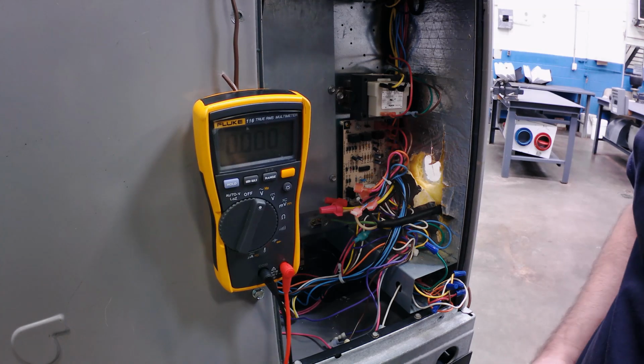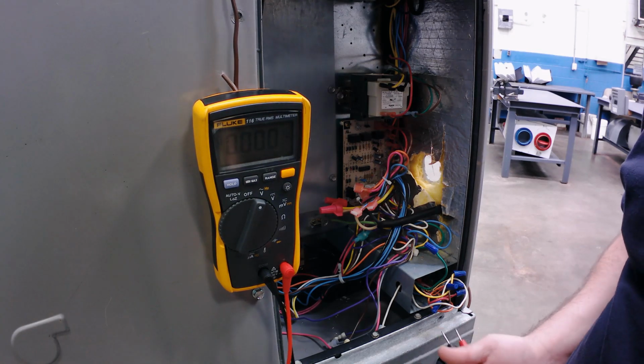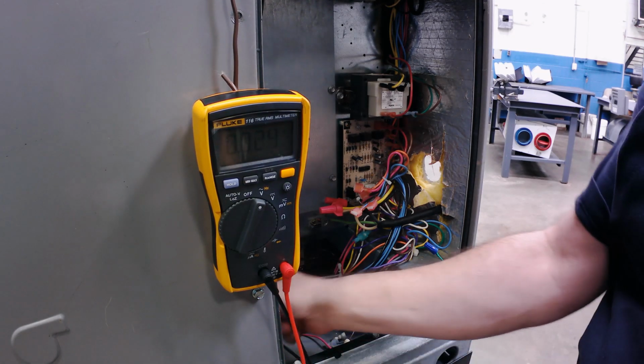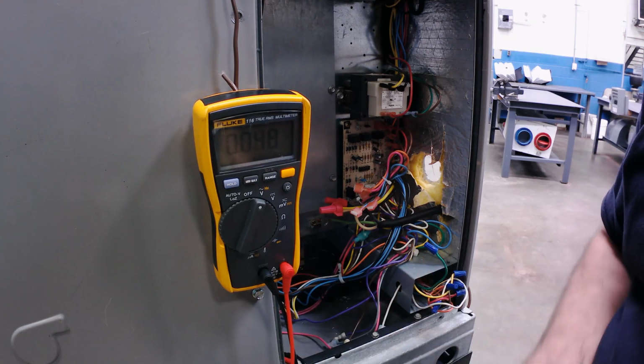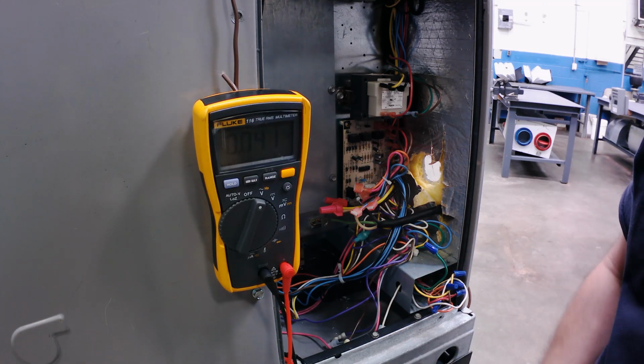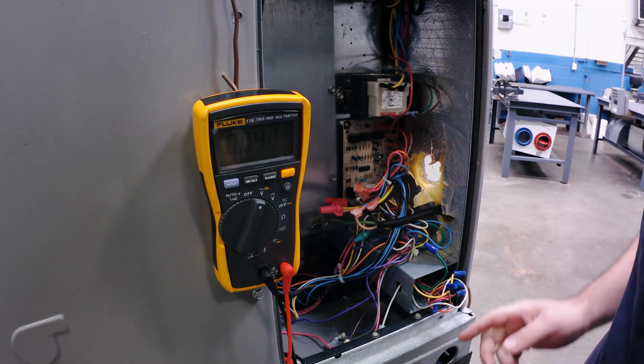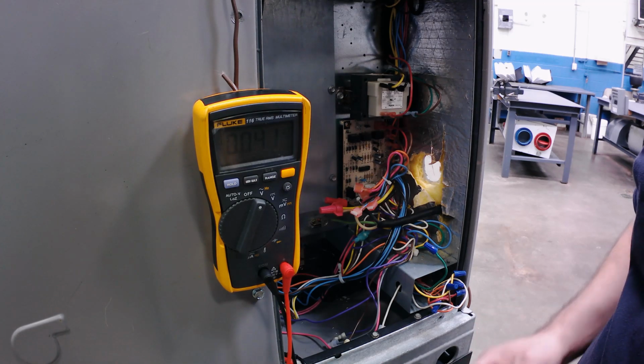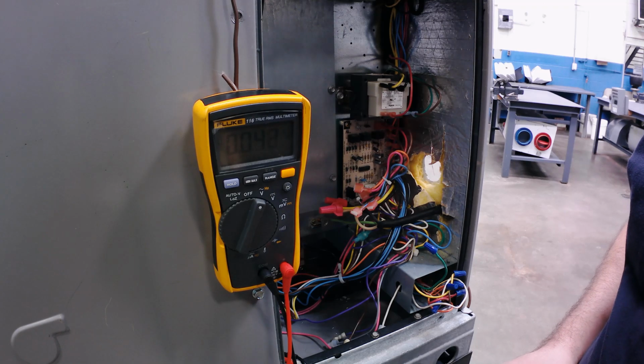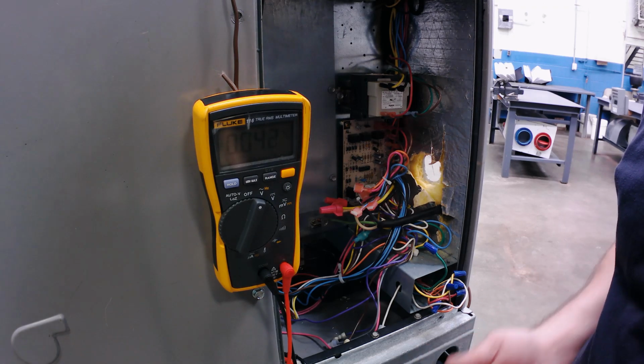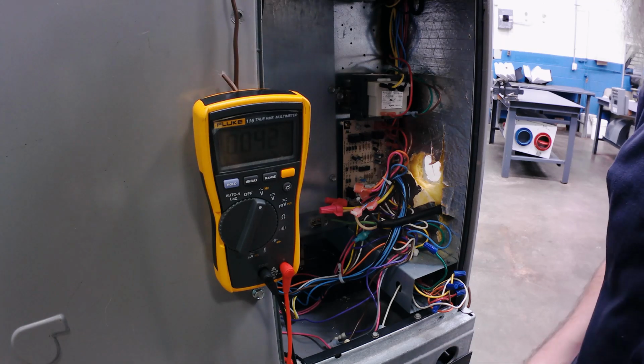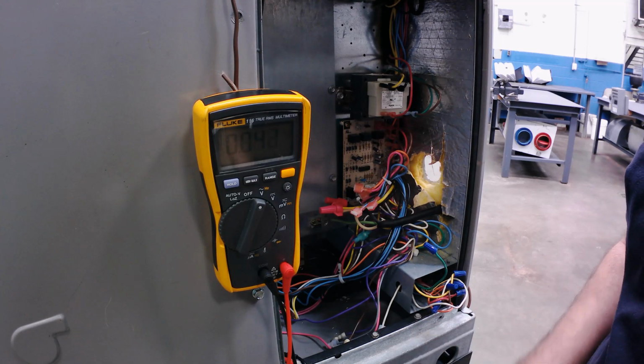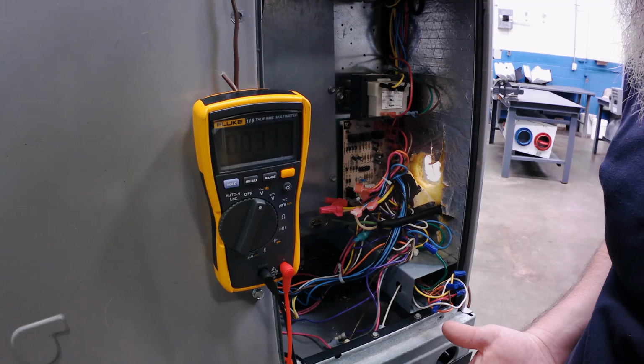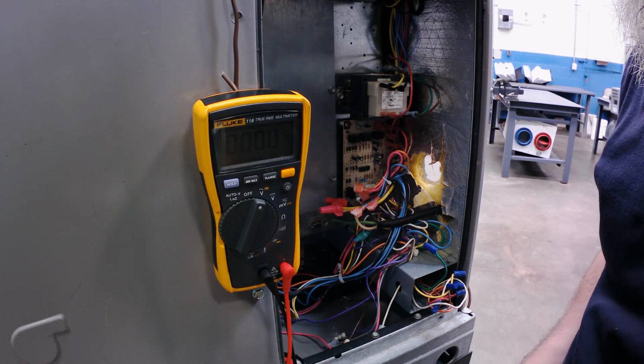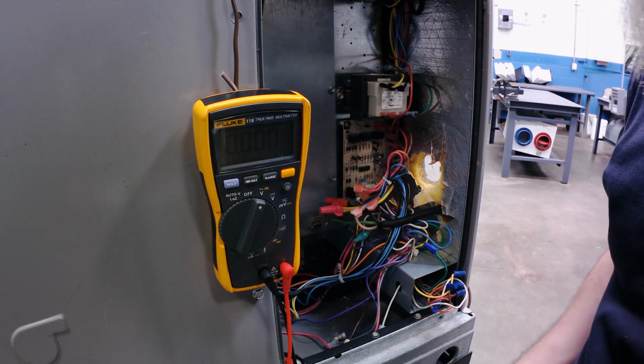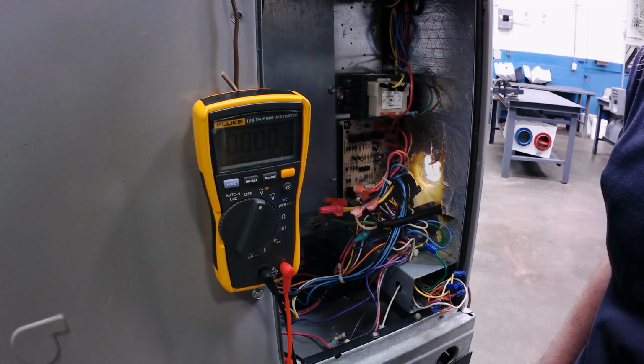So what I would do then is not blame the thermostat. It could be a bad thermostat, but it could also be a bad wire. What you need to do is a continuity check—I've done videos on that, I've preached about it enough. But don't just change the thermostat. Know what circuits you're involved with and check voltage. If the voltage isn't present, check continuity on the wire. If you've got a good wire and no voltage, then assume the thermostat isn't sending power and it should be replaced.